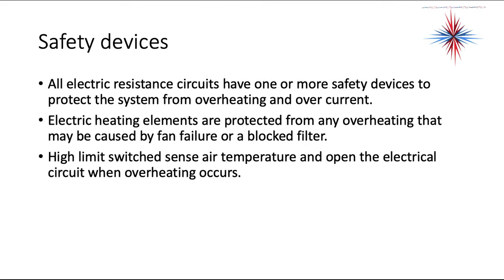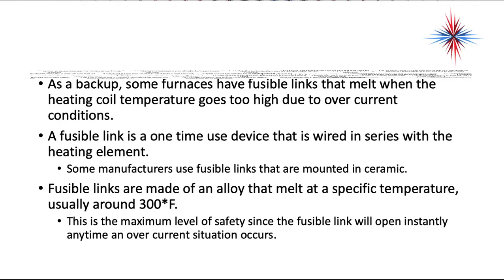This is a requirement, and if you ever have a bad high limit control that's preventing the heating from coming on, do not jumper it out. It is an extreme fire hazard. Even if it means leaving the customer without heat, you leave the customer without heat until you can get a replacement for the high limit.